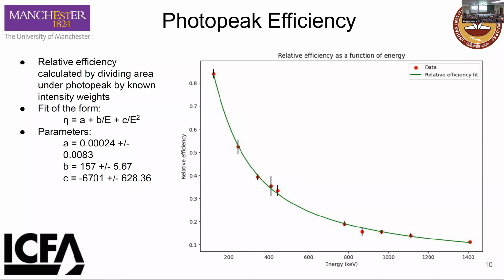The reason is that you expect the polynomial, but just going back down to the keV, we're missing a component of the spectrum. So it cannot be the exact answer. It cannot be negative. It should be positive. You use the detector with liquid nitrogen. What happens if you operate the detector without the low temperature? I'm assuming the liquid nitrogen cools the entire setup and reduces thermal noise from electronics or interaction with the material, which means more noise otherwise. I assume it would just reduce the resolution across the entire detector, but I'm not entirely sure.